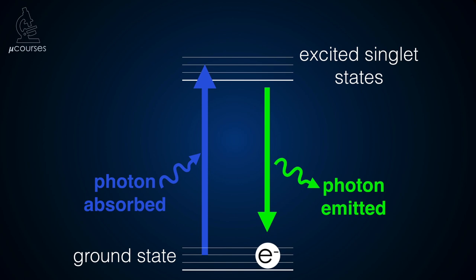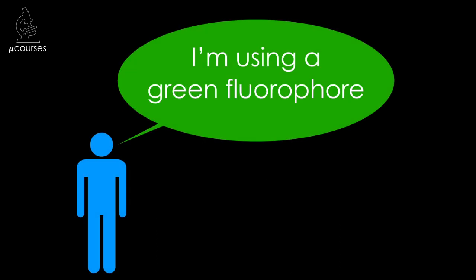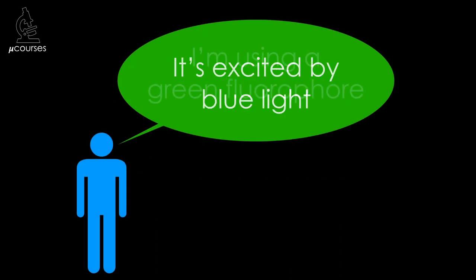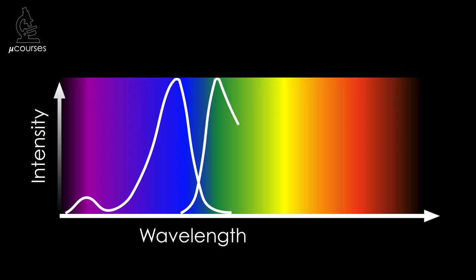In standard fluorescence applications, we simultaneously excite fluorophores and collect the emission using fluorescence filters. We often refer simply to the color of the fluorophore we're using, but fluorophores absorb light and emit light to varying amounts across the spectrum. Fluorophore spectra report the amount of light across wavelength that the fluorophore can absorb and the longer wavelengths that are emitted. Fluorophore spectra are different for each individual fluorophore.